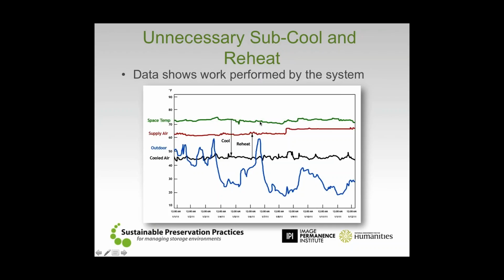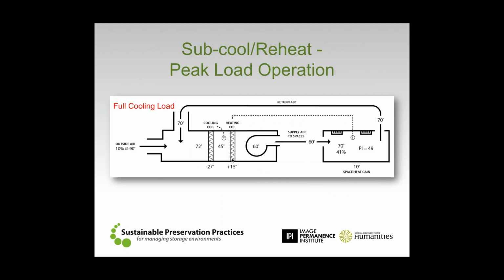So this is a good example where, because the system has been programmed to dehumidify, that scheduling, or looking at the logic control on that operation, is saying, well, there's no difference between summer and winter. And in this circumstance, we're going to subcool and reheat even in January and waste all this energy that is truly not doing anything for us. Now, another part that comes up in this, and this is a little bit tougher to achieve. It takes certainly paying attention, but it's not an insignificant deal.